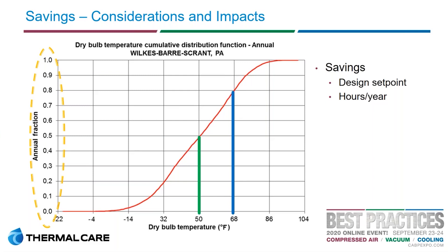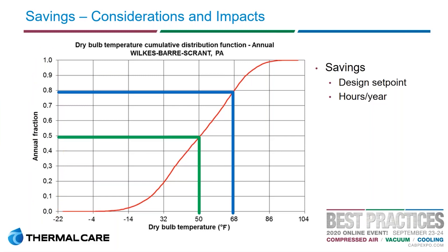The whole point of shutting the chiller off is that it's the major point of electrical energy consumption. The fluid cooler sitting outside to supplement as the free cooler uses significantly less energy. Based on these two points, we've actually gained about 30% more time per year where we can completely turn off the chiller by adjusting the set point. That 30% is a huge portion of the year — running a chiller is expensive, and leaving it off saves money. Ultimately, the investment in this free cooling system design will pay back for itself through these increased hours of operation.